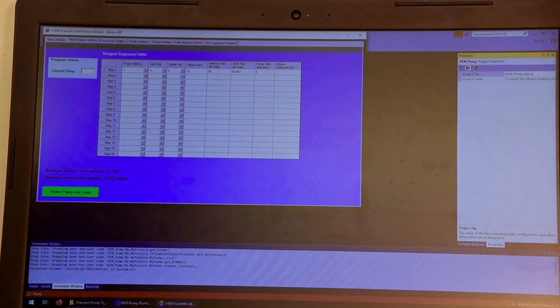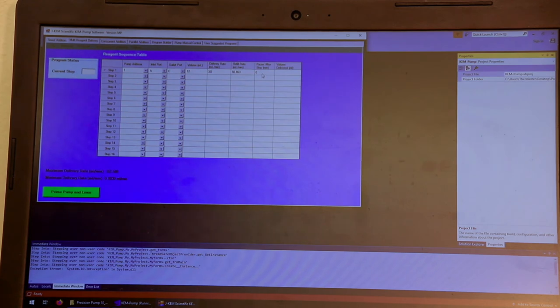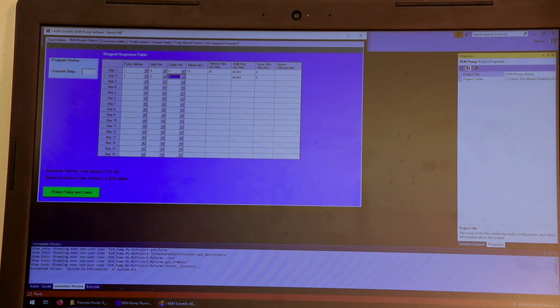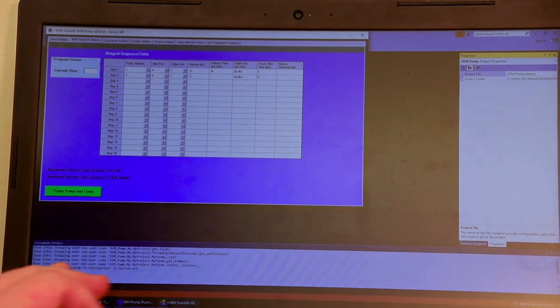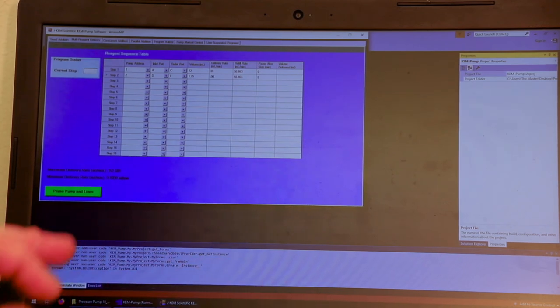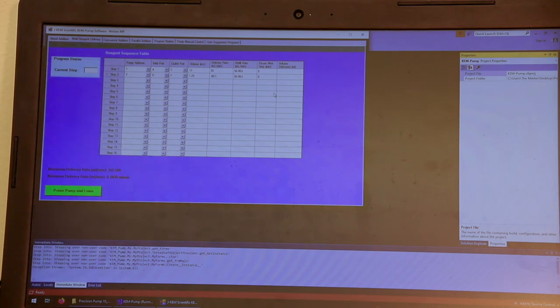and I want it to take 35 minutes to do that. I can even specify a pause of a certain amount of time after that delivery. And then after you've done that addition, I want pump two to go to port D, use that as its inlet. And then the outlet would be port F, and I want it to withdraw 1.25 milliliters. I want it to add that at a rate of 0.001 milliliters a minute. And so I can set up an Excel table with as many as 16 steps telling which pump to go to what port and fill with reagent, and then to go to what port and dispense.